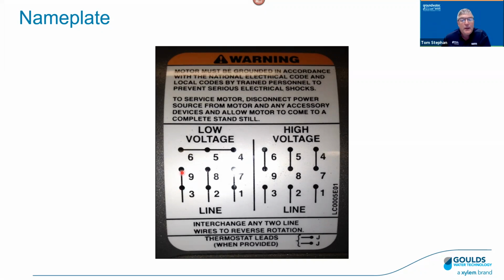Then we take 3 and 9, put those together, 2 and 8 together, 1 and 7 together, but we don't put a wire nut on yet because we're going to bring our power supply in to this area. So line 1, line 2, line 3 doesn't really matter, right? Because it's 3-phase. Just going to bring in 1 line here, 2nd line here, and then the 3rd line here. So now you're going to wire nut those together. So wherever there's a wire nut, you should have 3 wires, right, for low.